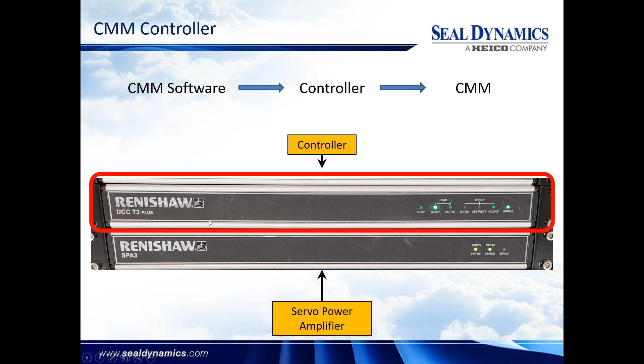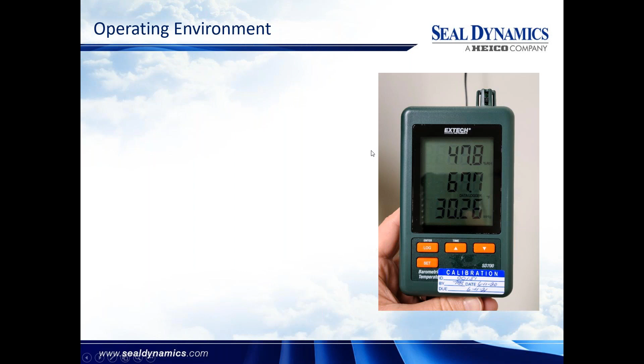All right, operating environment. All metrology departments are typically under a controlled environment. A lot of manufacturing shops have a controlled environment because the tolerances they're trying to hold on the product they're making can't be maintained if your shop floor temperature is fluctuating 10, 20 degrees or something of that nature. So temperature and humidity are probably the most critical, or at least that they're stable. Depending on the company you talk to or the ISO standard, the standard temperature is often 20 degrees Celsius or 68 degrees Fahrenheit.